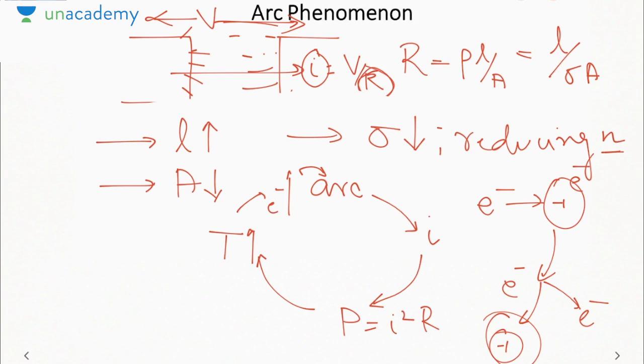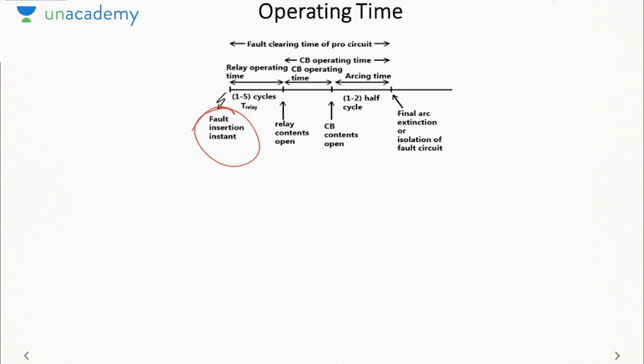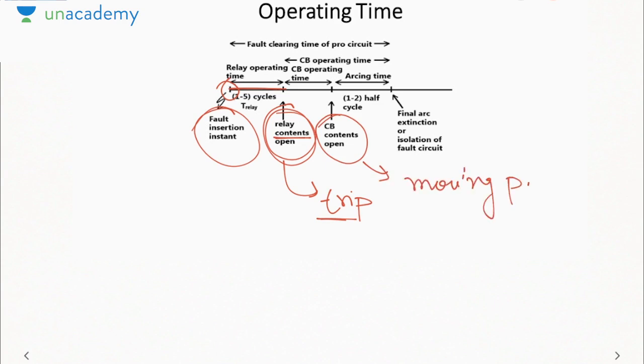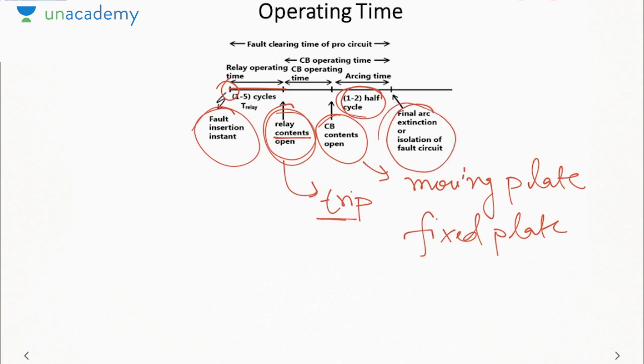Hence, the entire phenomenon in protection is not limited to just sensing by the relays and opening the circuit by the circuit breaker. There is a third event involved which constitutes extincting the arc, or arc extinction. Okay, there is a third phenomenon. So if we see the total time that it takes to clear any fault, suppose a fault occurs at this instant at t equal to 0. In 1 to 5 cycles, the relay contacts will open and send a trip signal to the circuit breaker. In the next 1 to 2 cycles, the circuit breaker contacts will open and separate the moving plate from the fixed plate. But as the moving plate separates from the fixed plate, what happens? An arc will be formed, and after 1 to 2 half cycles, there will be final extinction of the arc.